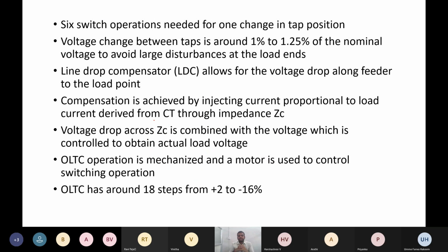Then the voltage change between taps is around 1% to 1.25% of the nominal voltage, to avoid large disturbances at the load ends. So what does it mean? As I told previously, because of the voltage difference, current will flow from S1 to S2. Because of this voltage change between two taps, either between tap 1 and 2, 2 to 3, 3 to 4, 4 to 5, anything.